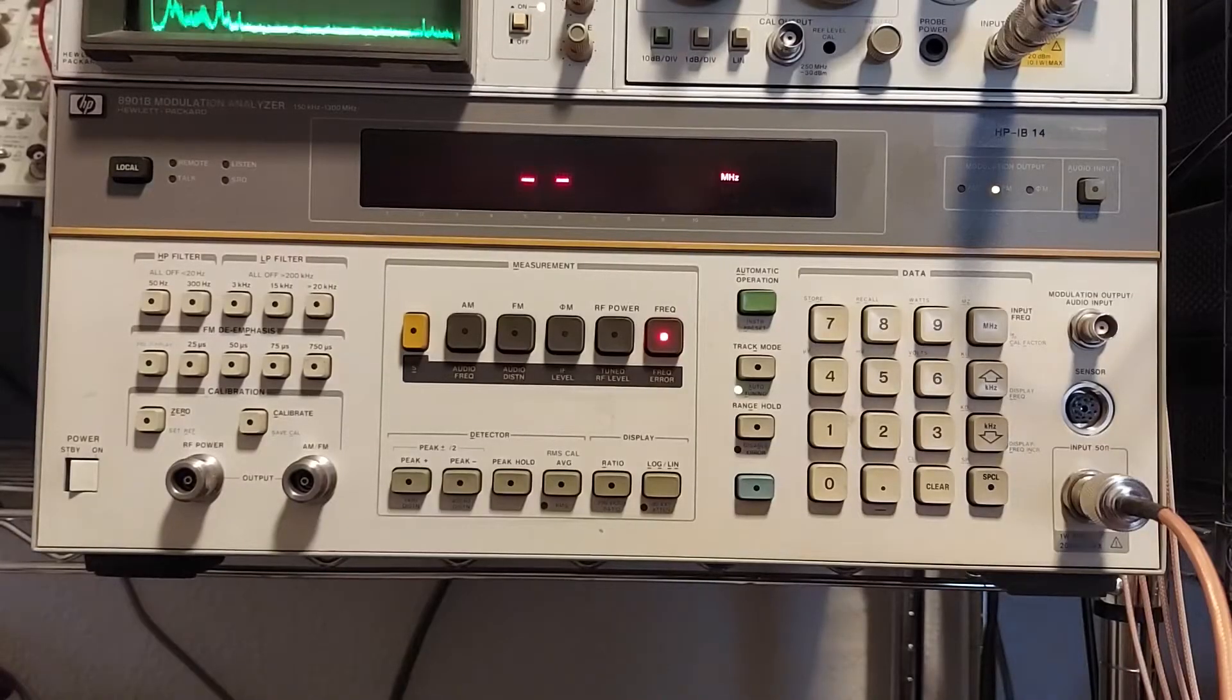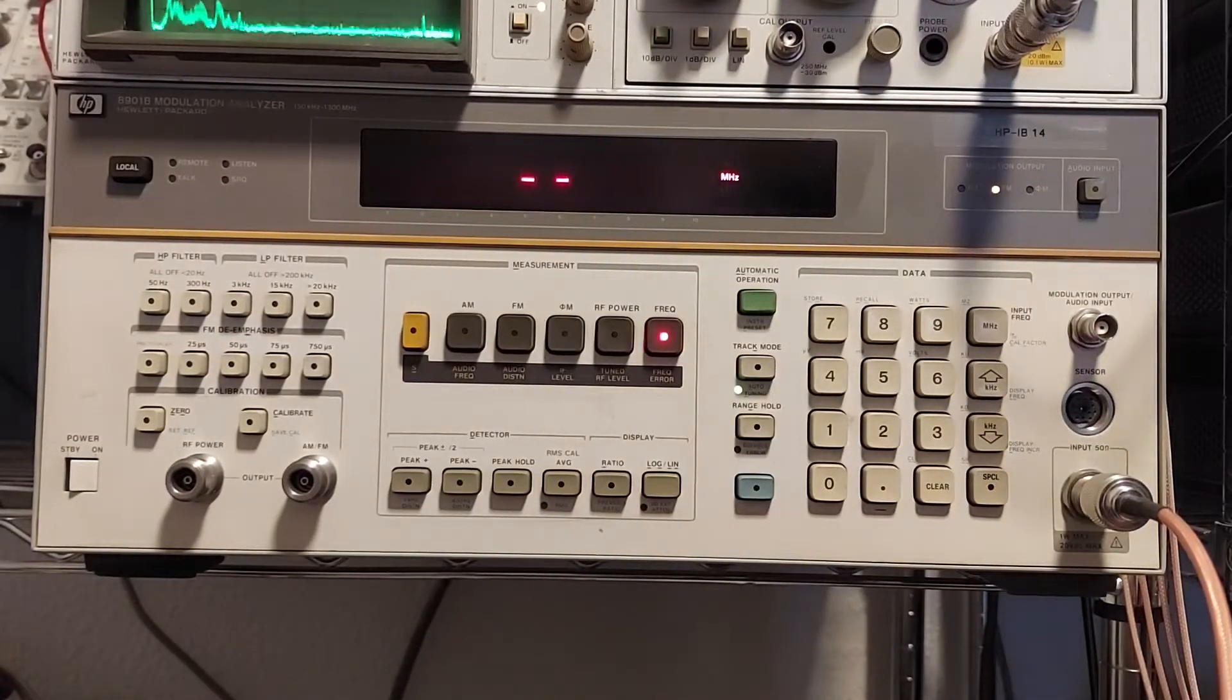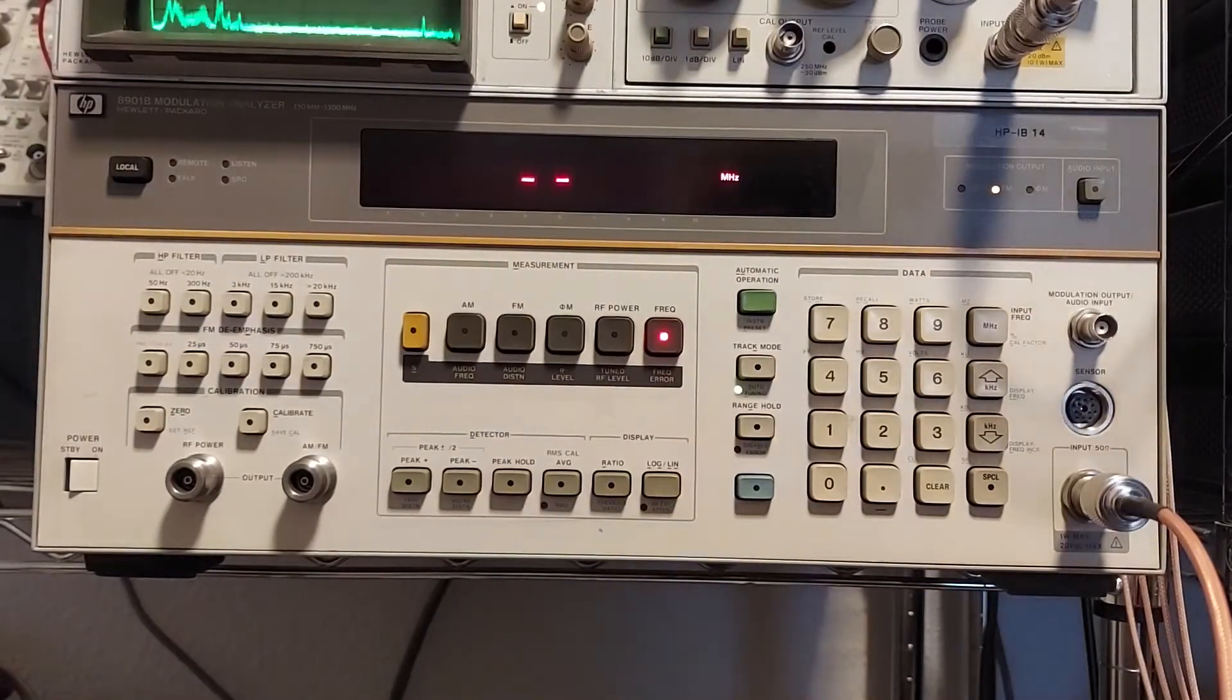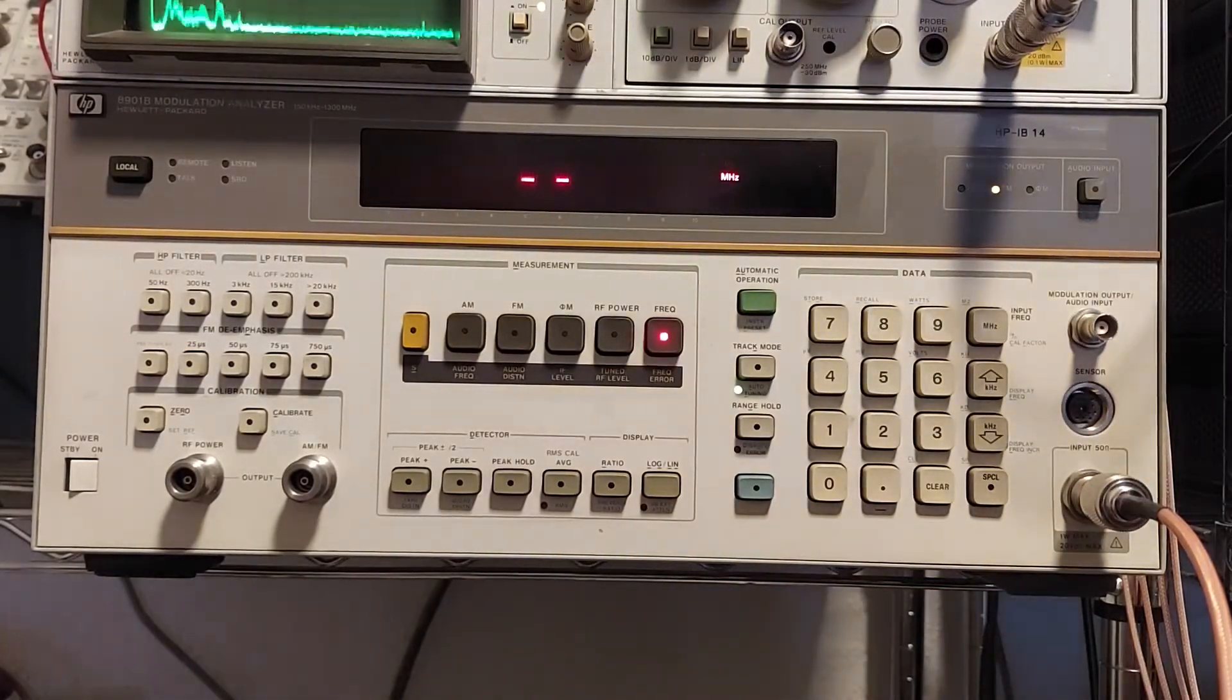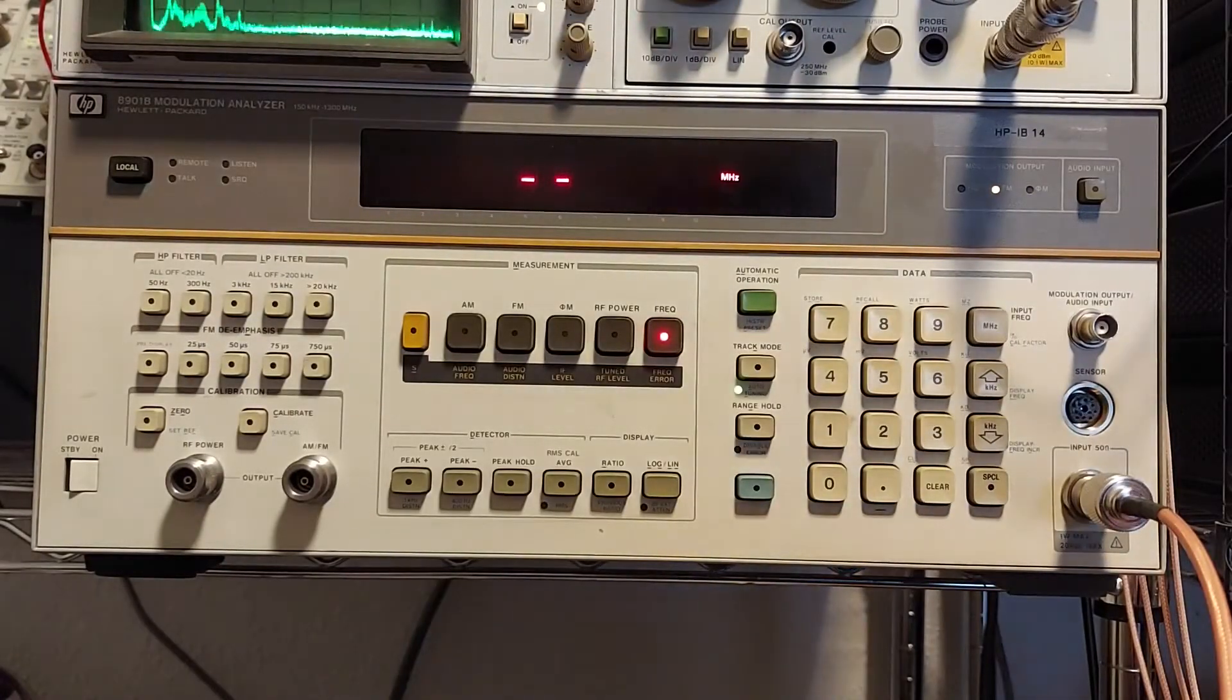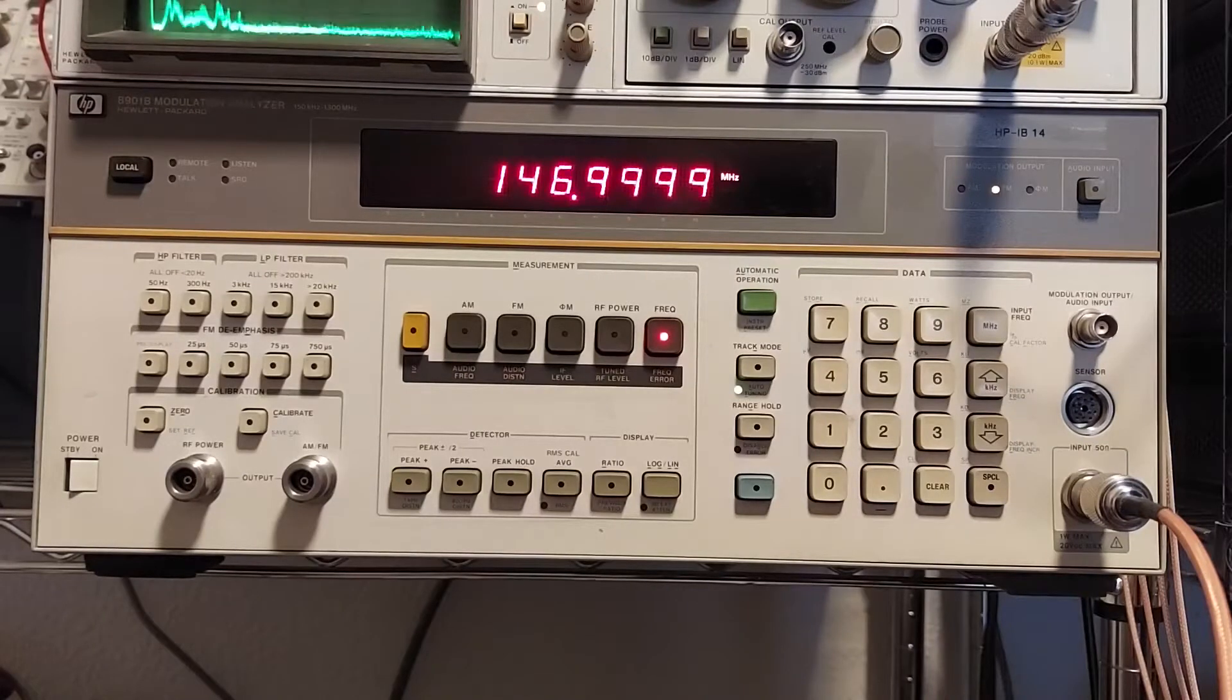Now, since I'm still learning how to use this instrument, I'll just go through some of the basics. So when you first turn the instrument on, it comes up into this condition here, which is basically called instrument preset. And now I will turn my signal generator on. And it automatically searches and locks on to the frequency.